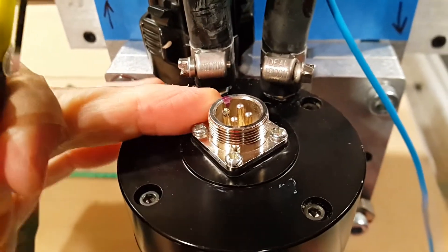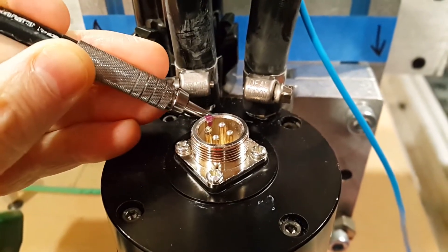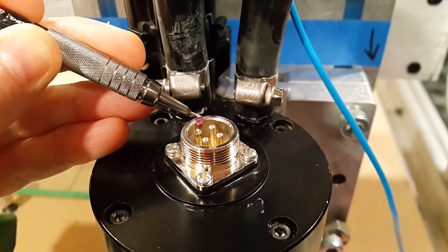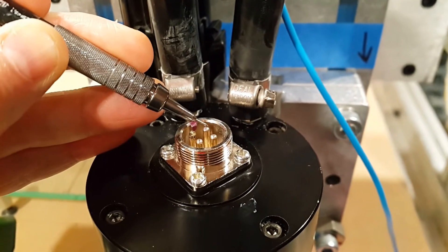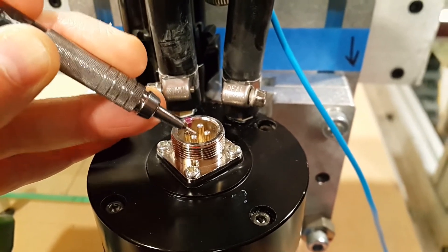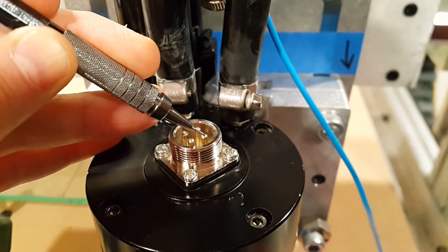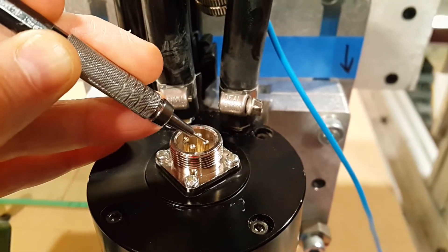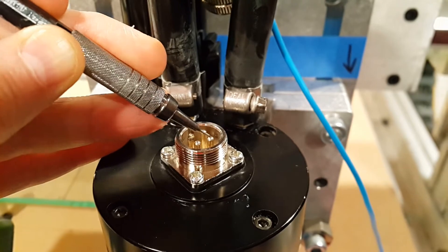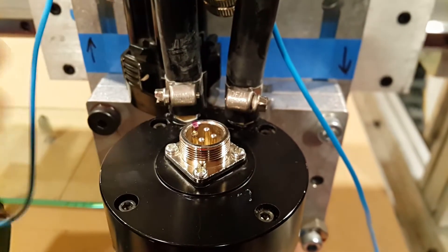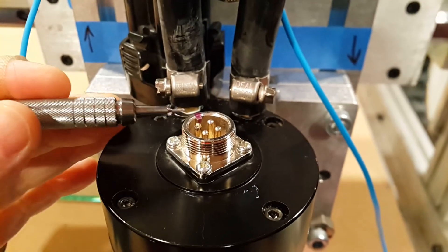So this is the task at hand. This is obviously the top of the spindle, this is the main connector. We have three leads here: this lead is the W, this is the V, and this is the U. And then this pin is left floating in this instance. Sometimes on certain spindles it's connected to case ground of the spindle itself. In this case it's not, it's just not connected to anything.